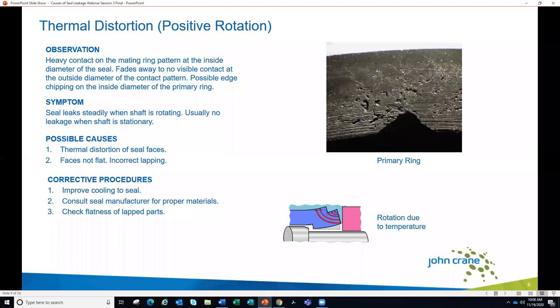Like on the previous scenario, this can also be caused if the faces were not correctly lapped or adequately flat when installed. It's imperative that we're doing a good job not just with the lapping process but also checking that it was performed correctly. If we've ruled out lapping as a cause and it is thermal distortion, then we want to check how well we are cooling the seal. This is normally done through the use of a support system — there are a number of API flush plans used to flush, cool, and lubricate the seal faces, and we want to make sure the support system is able to handle the heat load.